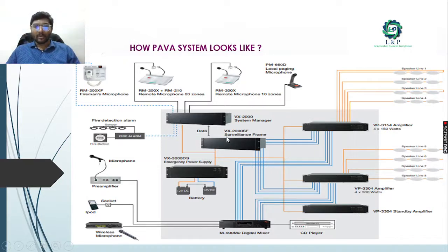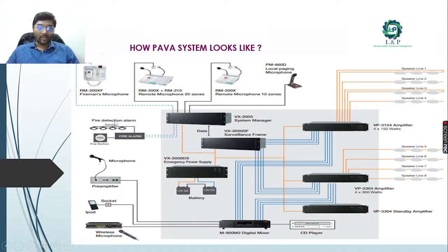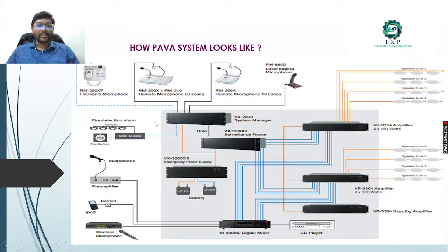The fire detection alarm is the most important component because once received, the evacuation process must begin. Whatever is happening through the speakers, this signal is given the highest priority. It is connected to the system manager, and the fireman microphone is also connected to the PAVA system. If a fire alarm signal occurs from these two, it is given the highest priority and the evacuation scenario begins.